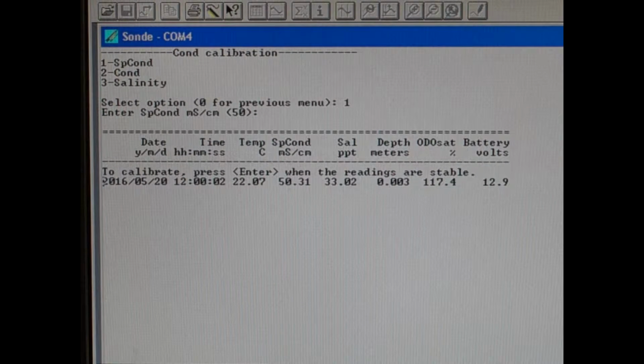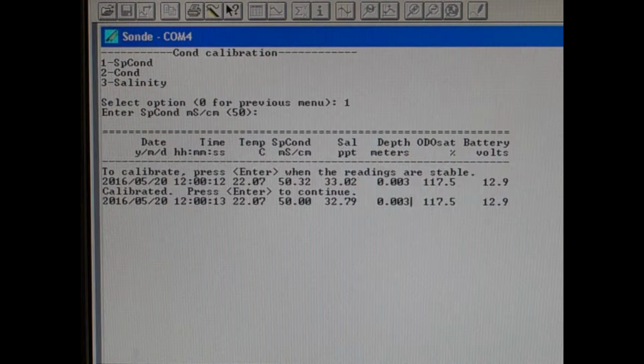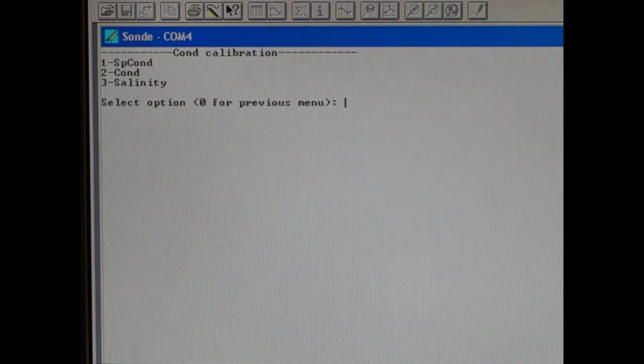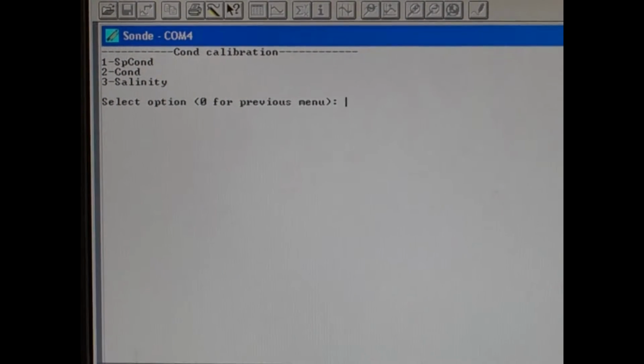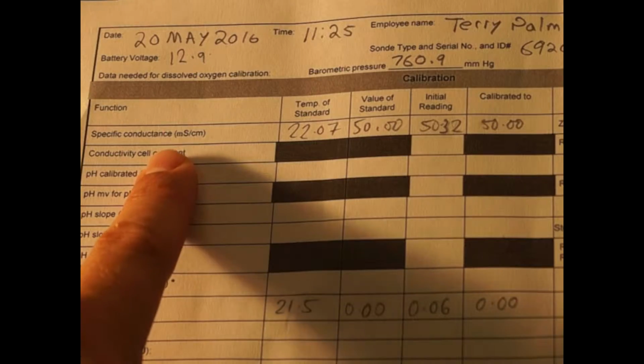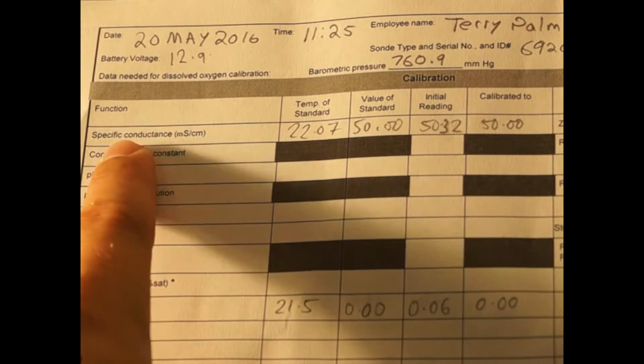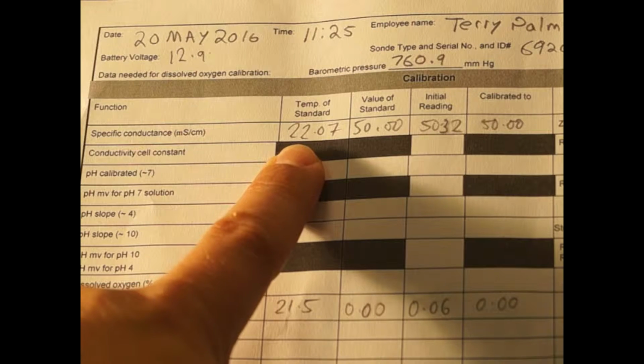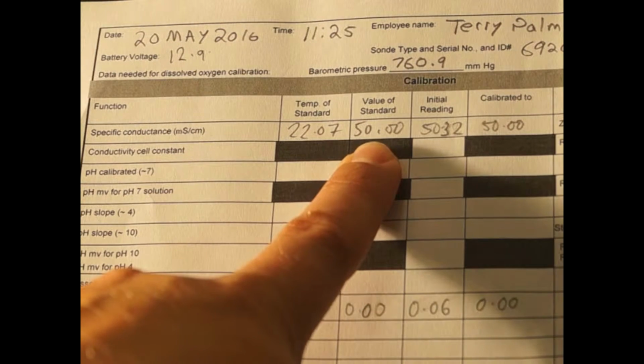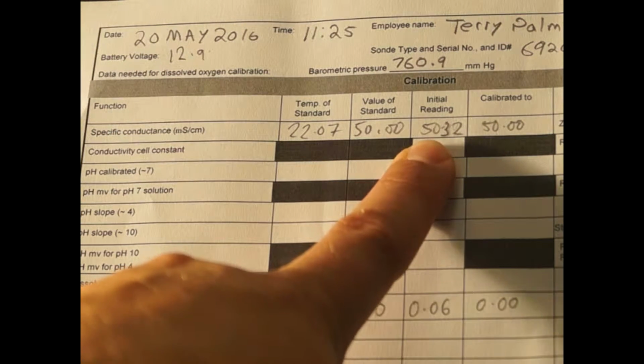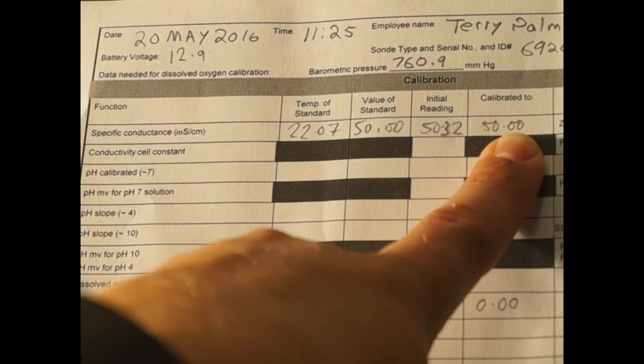Both of those we write down on our calibration sheet. Now we push enter. Now we write down the post value, which is 50.00 on the calibration sheet. And we have now calibrated our conductivity. Okay, so now back on our sheet to verify for specific conductance. This is the temperature of what we found on the Sonde. This is the value of our standard, which is 50. The reading was 50.32, and we calibrated to 50.